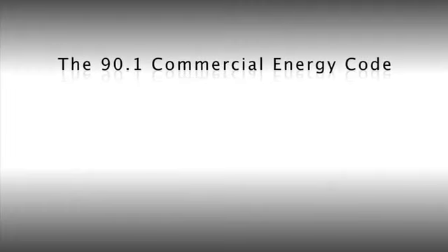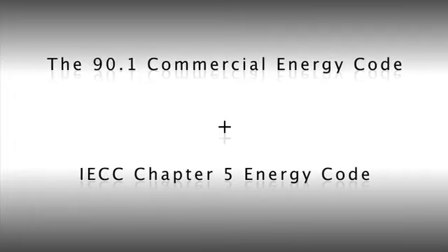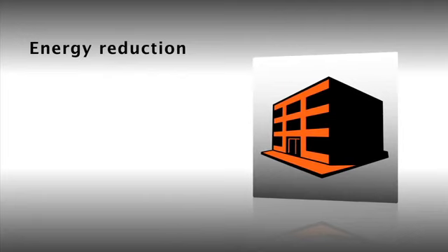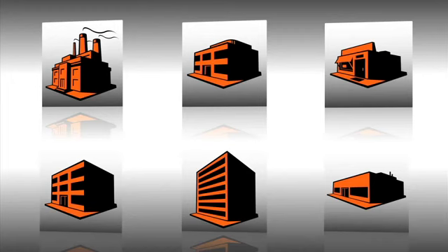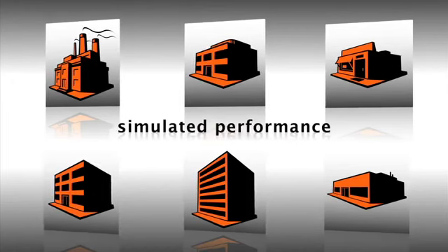The 90.1 Commercial Energy Code, along with IECC Chapter 5 Energy Code, focuses on energy reduction for non-process loads in these four major areas: envelope, interior lighting, exterior lighting, and mechanical. 90.1 Commercial Energy Code compliance can be demonstrated in several ways: prescriptive, simple trade-off, or simulated performance.